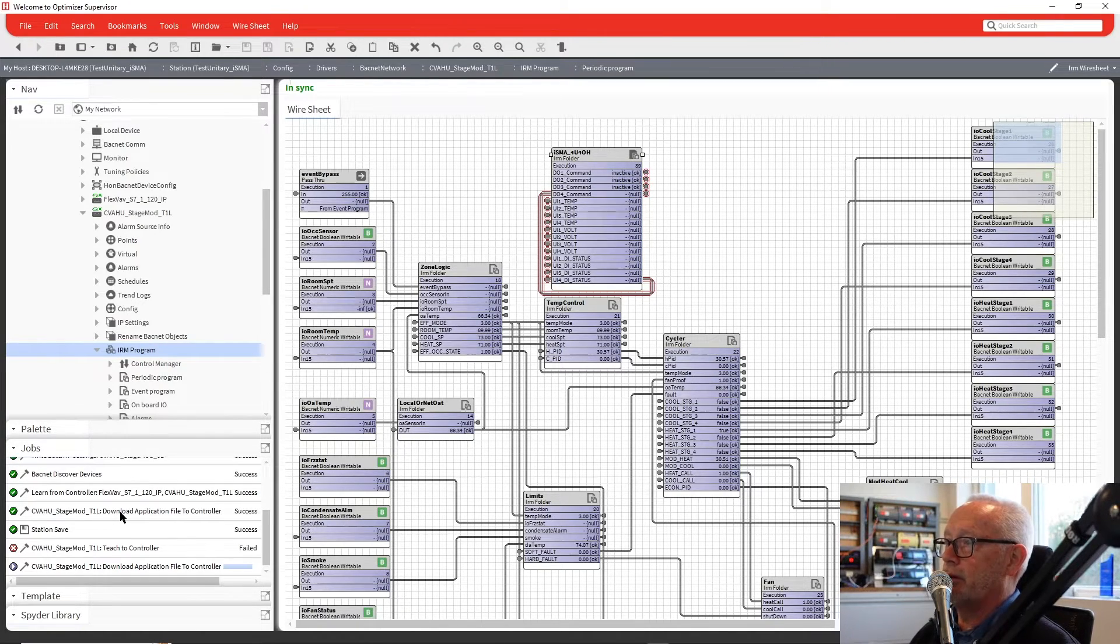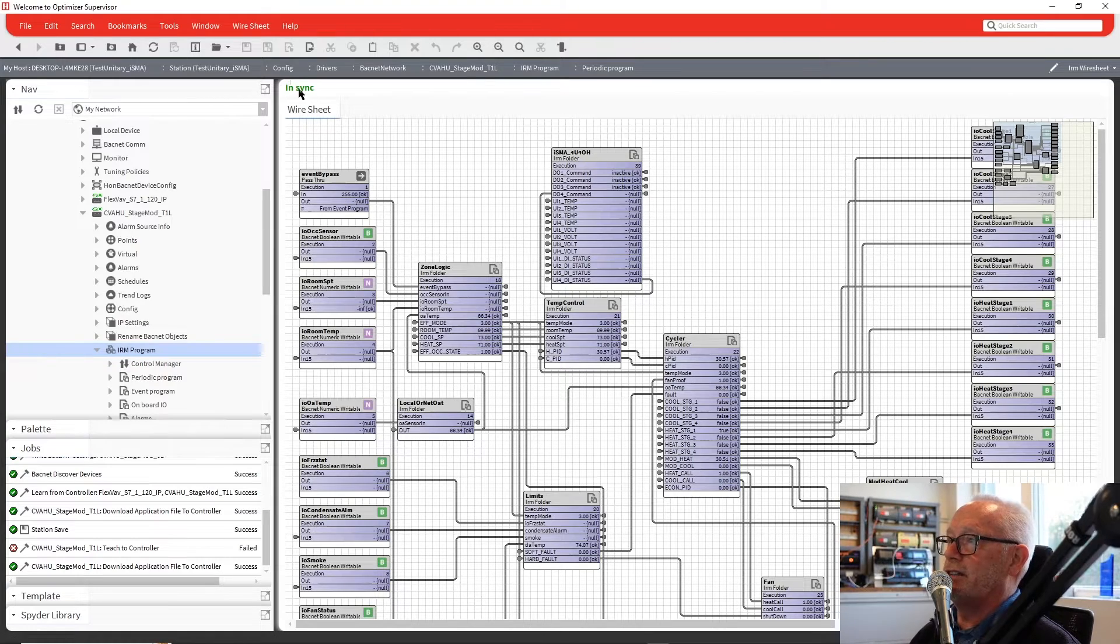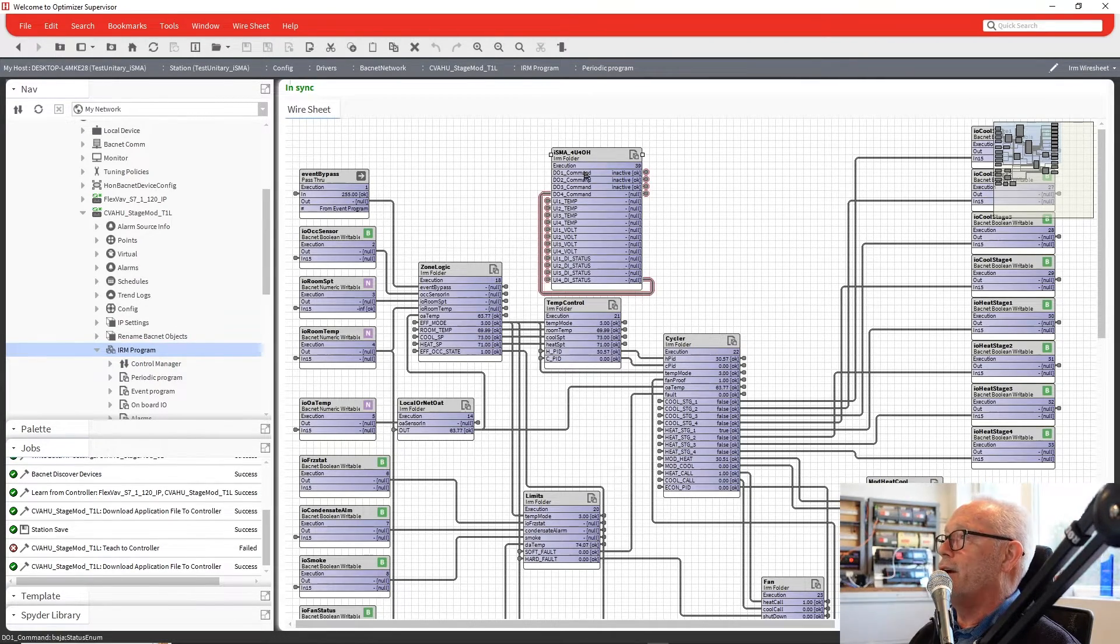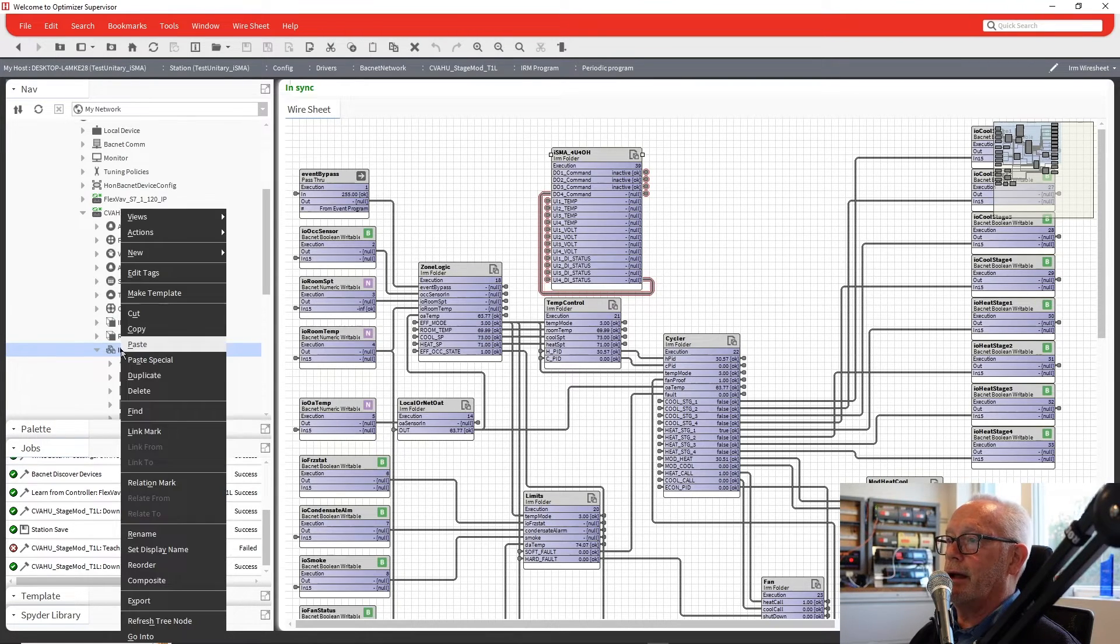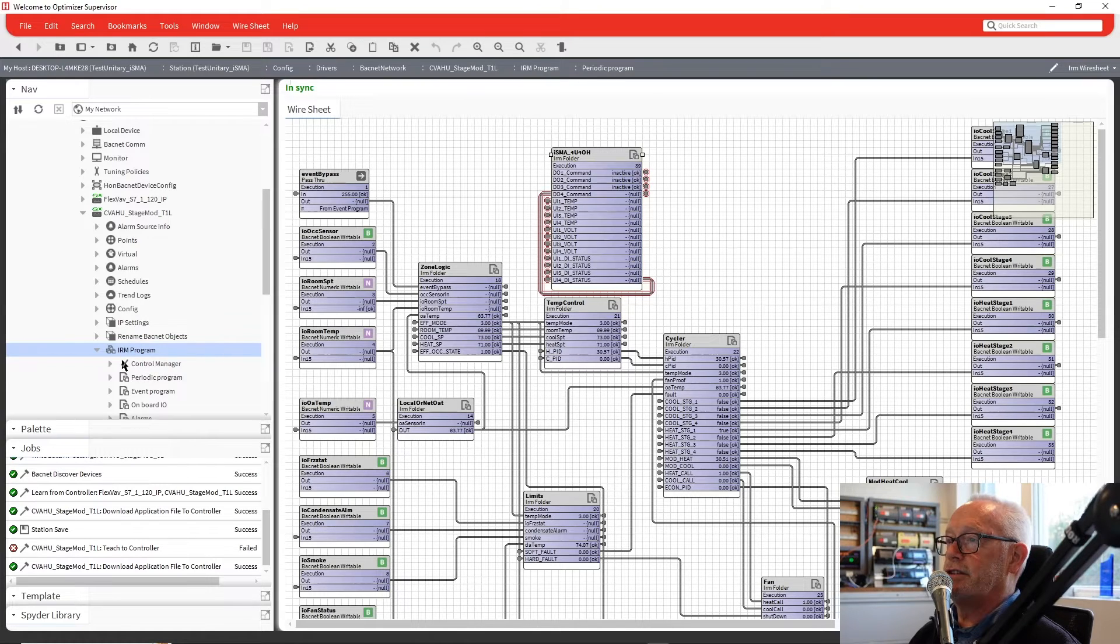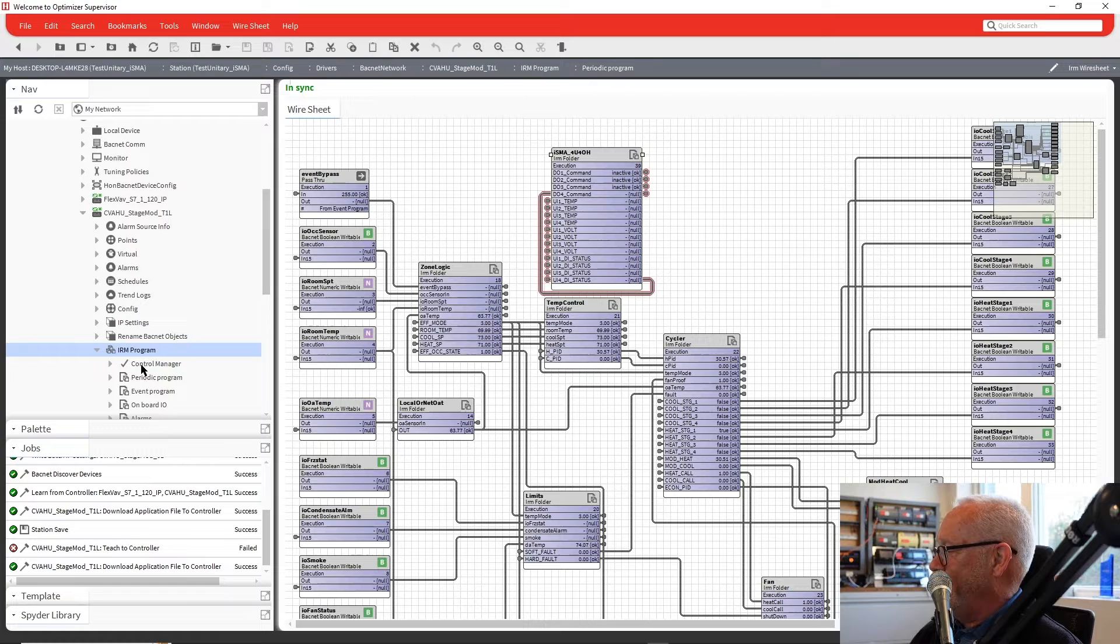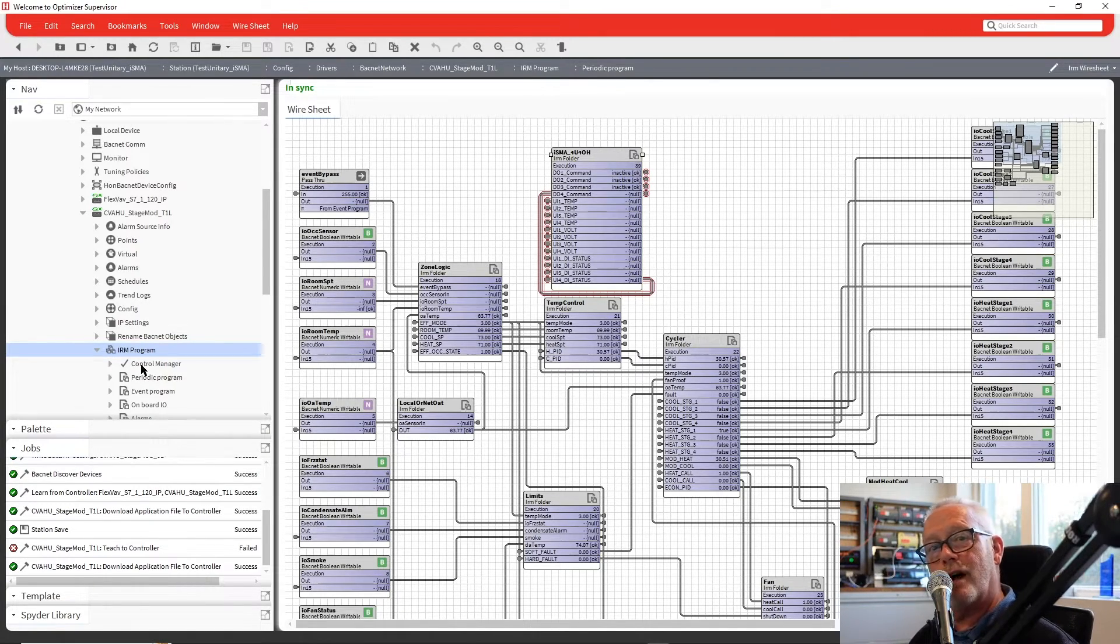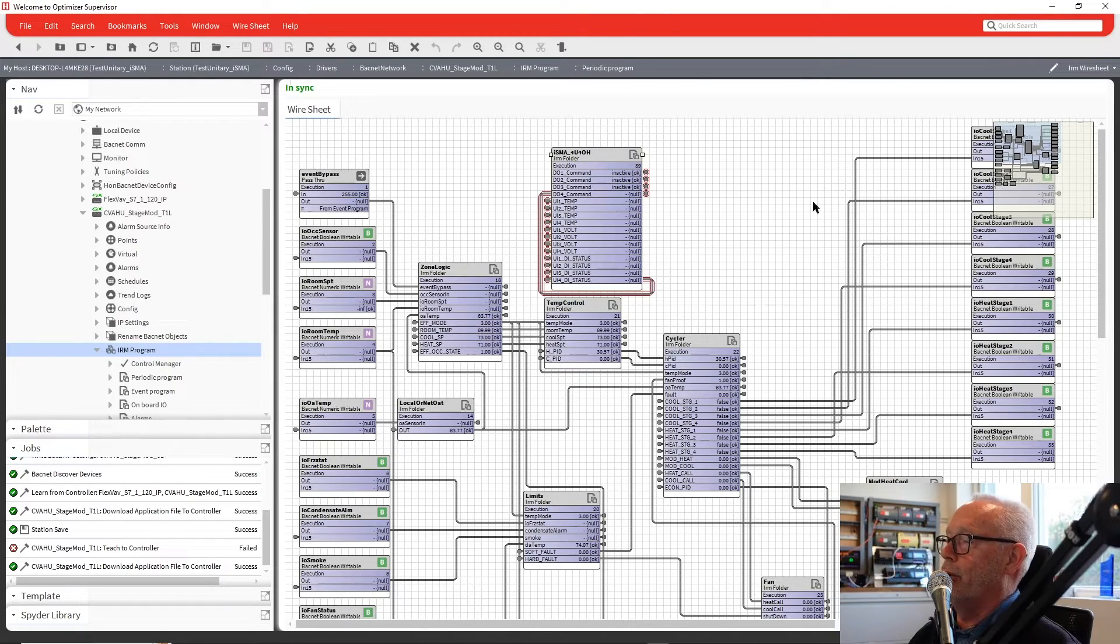When it's all said and done, we'll be able to work with this controller. Now I see it does say it's in sync at the top. It is successful. So now we have our controller downloaded. I can go over here, refresh my node. The check mark next to control manager, it is connected. I'm looking at the RS-485 LED on the controller and it's green, meaning that the Modbus 485 port is talking to the controller or to the IO module.